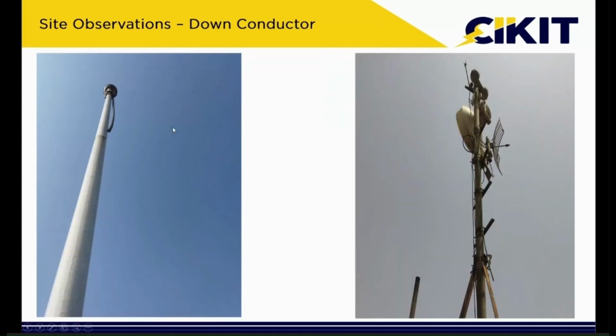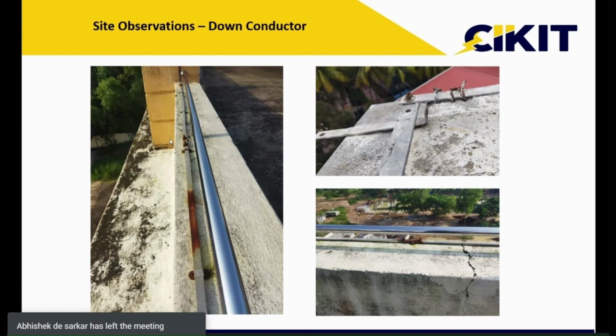Here you can observe that in both the cases, the cable got disconnected. There is no proper connection to this earthing. Here, if you take this lightning protection system, the most important thing is the equipotential bonding.